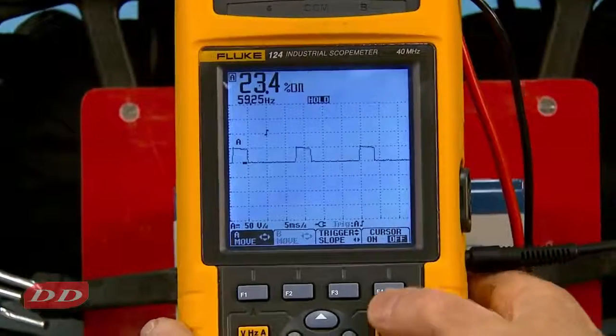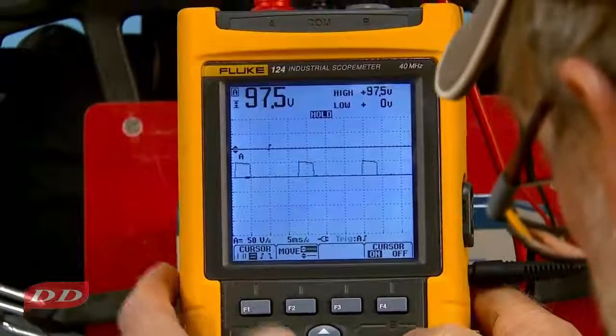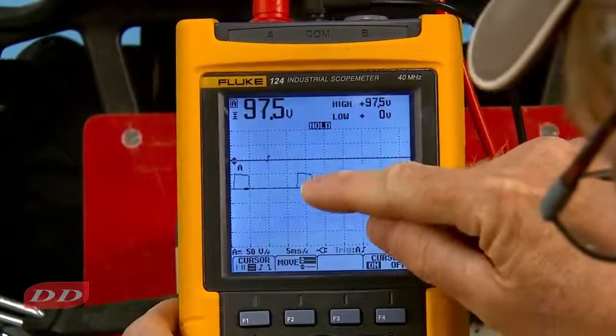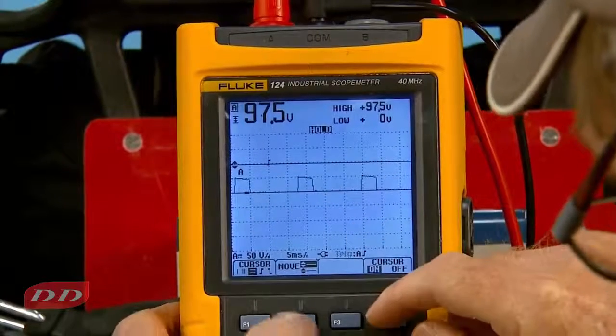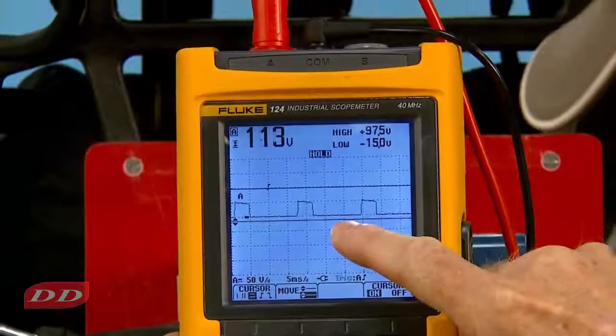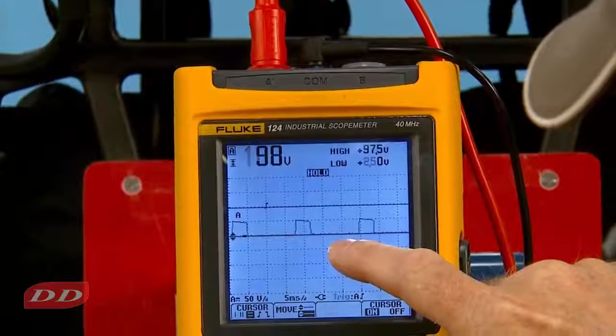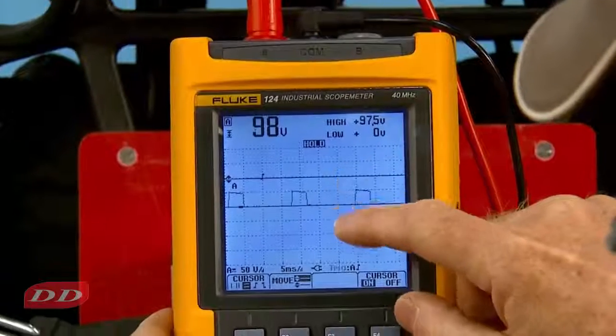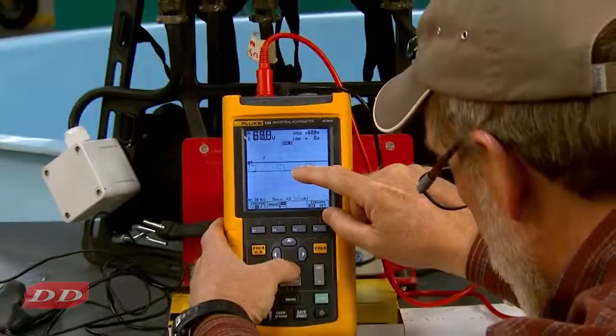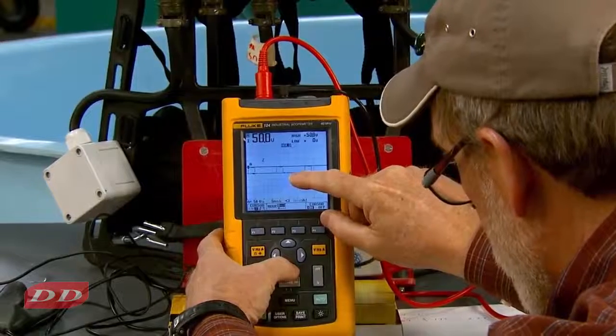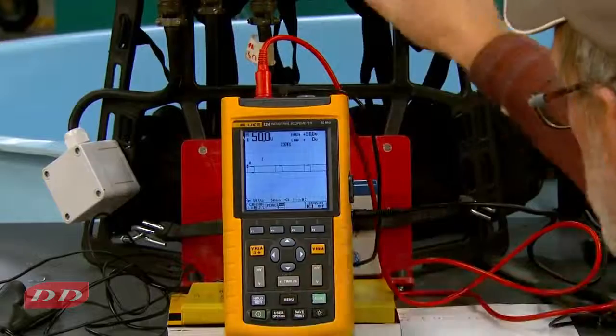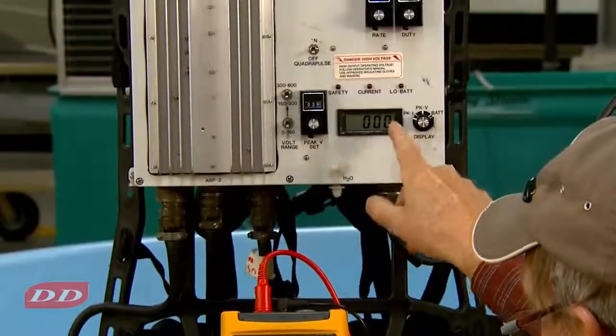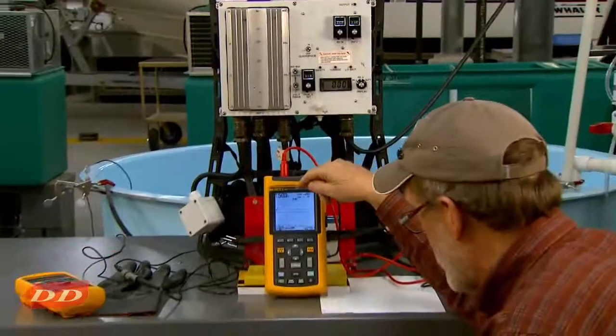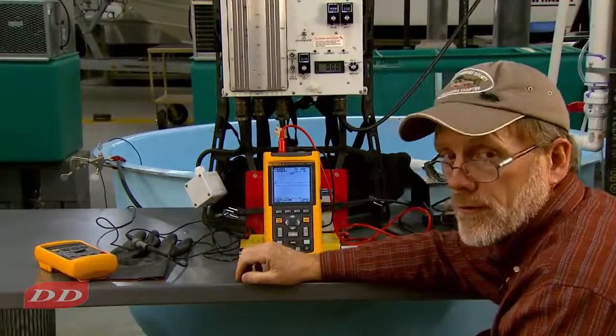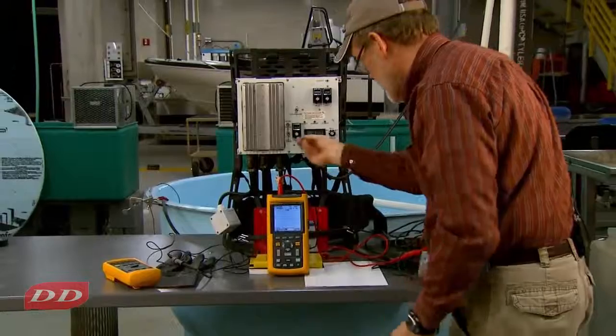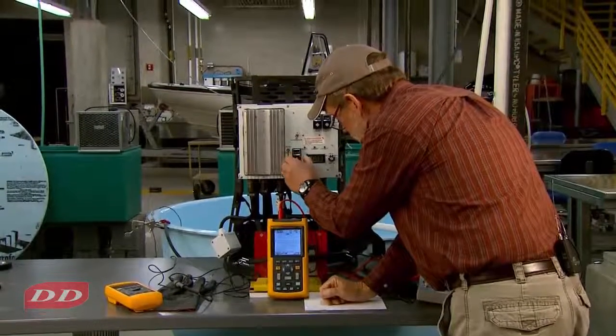So one way to check that is by something called cursors, and we can move these cursors to anywhere on the waveform we want. There's one cursor that's actually on the 0 line. I'll move it down. It was on the 0 line. Now I'll move it up to be exactly on the 0 line. And then I'm going to move this top cursor down to where it's at the top of the waveform, because we're interested in peak, because these are peak readings. And that pretty much does it, and it says 50 volts. So we dialed in 50 volts. The voltmeter said 50, 52, 51 volts. And then the scope meter gave us that, yes, that's true, it was 50 volts. So that's a check. That's a good reading. So we'll go again now to 100 volts.